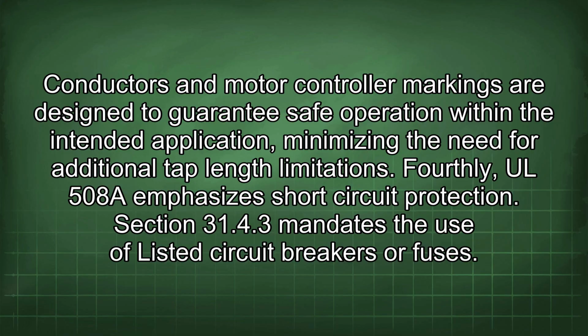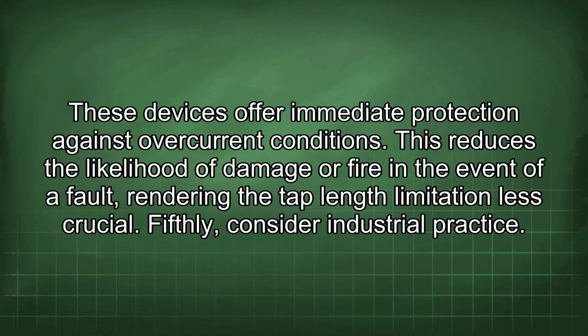tap length limitations. Fourthly, UL 508A emphasizes short-circuit protection. Section 31.4.3 mandates the use of listed circuit breakers or fuses. These devices offer immediate protection against overcurrent conditions. This reduces the likelihood of damage or fire in the event of a fault, rendering the tap length limitation less crucial. Fifthly, consider industrial practice.